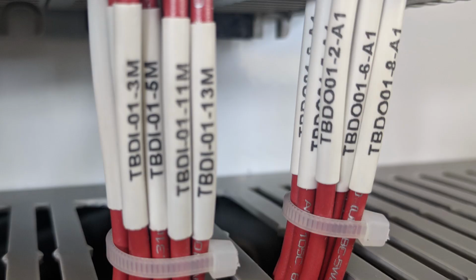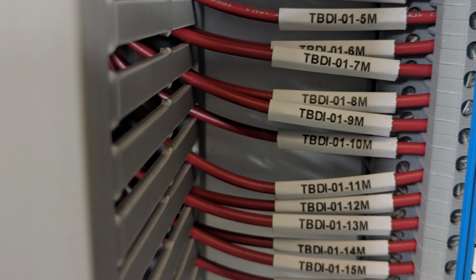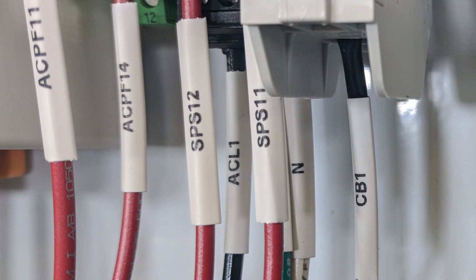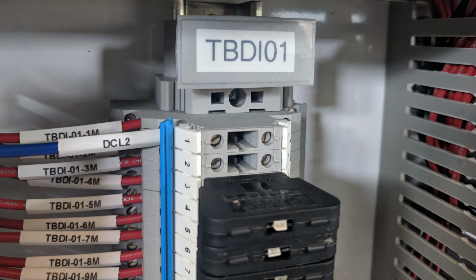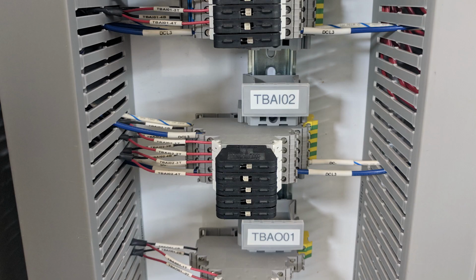We also really want to take a close look at how the panel and all the wires have been labeled. This is really, really critical, especially if you're building a panel that intends to be UL listed. Labeling is very, very critical. So we want to look at all of the terminal blocks within the panel, make sure that they are wired properly. Then the terminal block sections are very commonly labeled. We want to make sure that those are labeled properly.